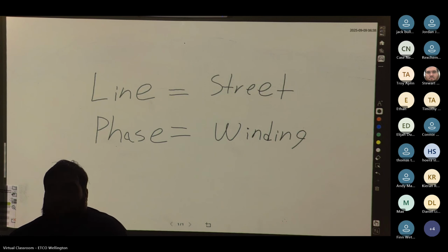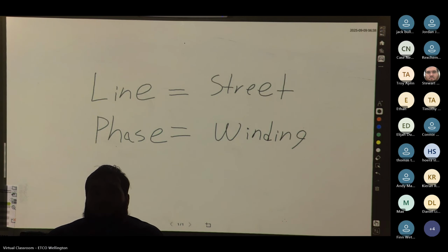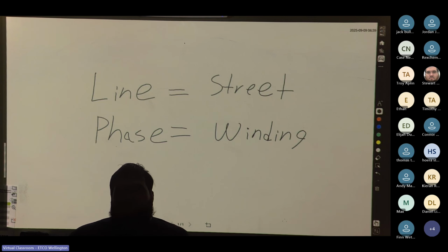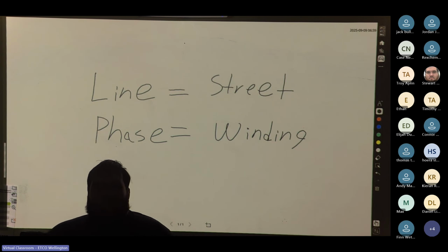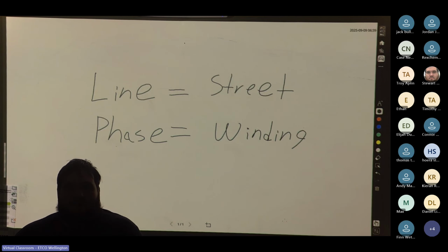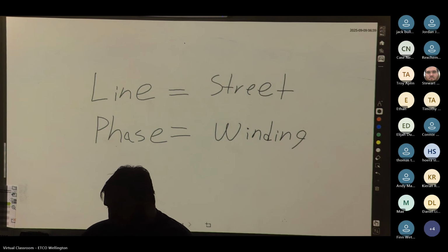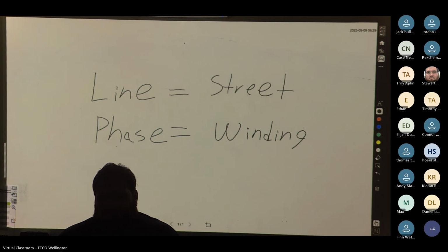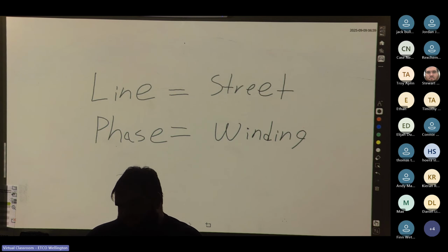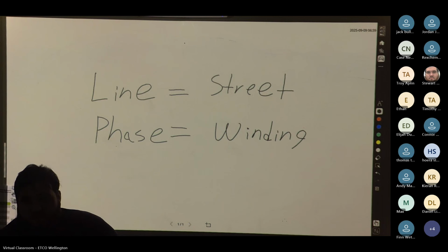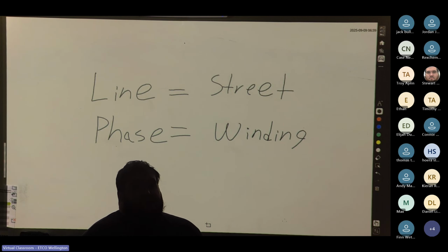Cool. If you measure one phase to neutral, yes. So if you measure from phase to phase, you get 400. You measure from phase to neutral or phase to earth, you will always get 230 on a standard site. That is because if there is a neutral, it's a star connection. Star is a lot more common.